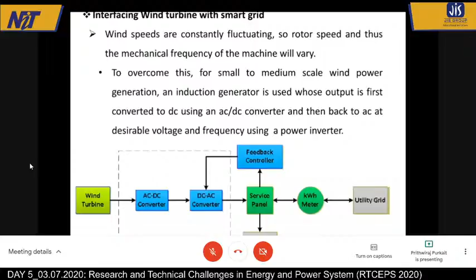For big wind generating systems, large wind turbines, a device called a doubly fed induction generator (DFIG) is used, where the stator means it's a slip ring or wound rotor type induction motor. The stator gives the three-phase output, and the rotor is also supplied with electricity through the slip rings, which get their electricity from the grid through an IGBT converter. That's why it's called a doubly fed induction generator, and it's used to produce electricity in big wind turbines. It also consists of an AC to DC and back to AC converter to make the output suitable for connection to the grid.